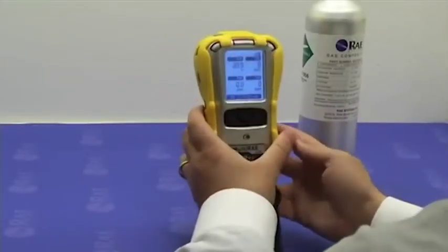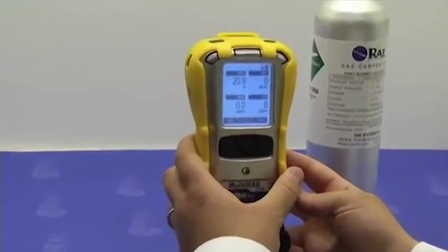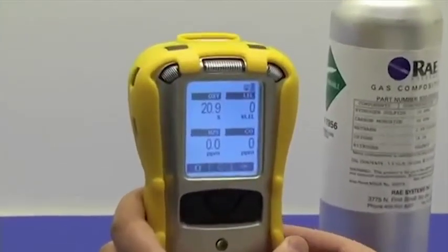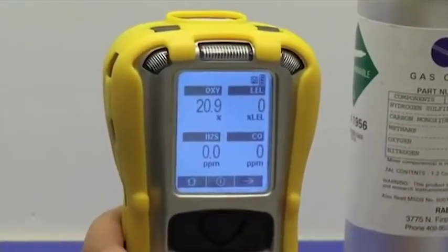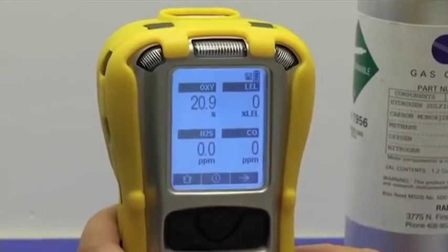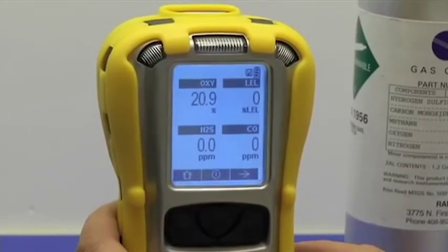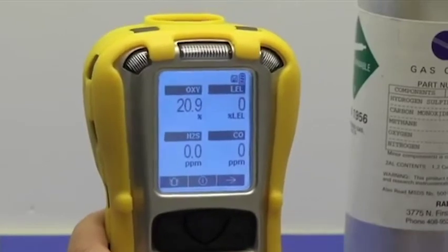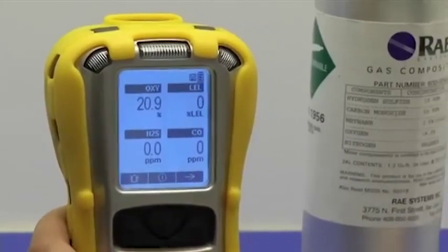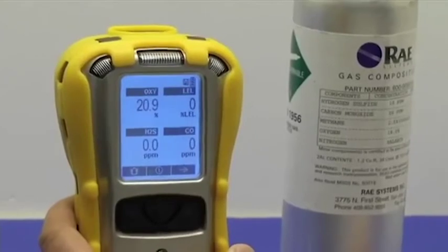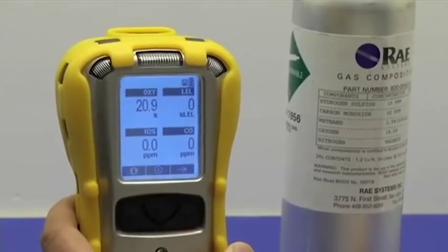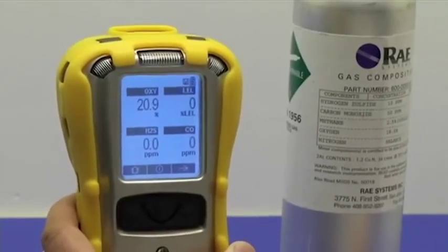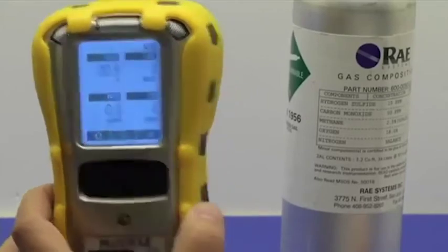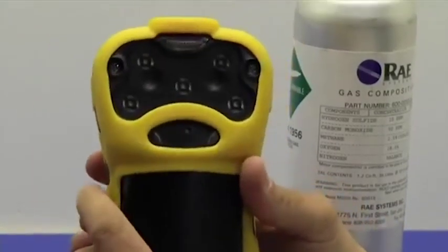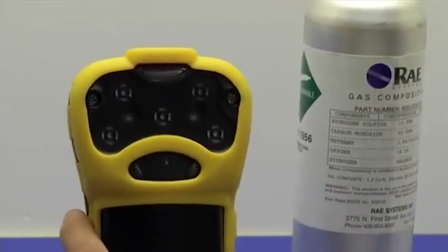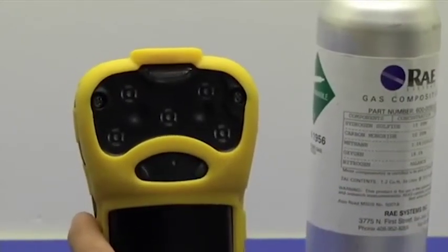The same approach applies when it comes to bump testing the diffusion versions of the new MultiRAE. The instrument I'm holding in my hand has 4 sensors installed: oxygen, LEL, H2S, and CO. So we'd bump test it with a 4 gas mix, all in one go. The difference between the pumped versions of the MultiRAE and the diffusion versions is the diffusion version gas inlets are located on the back of the instrument, and the calibration adapter also looks slightly different.